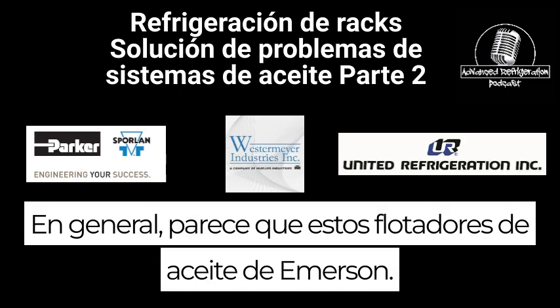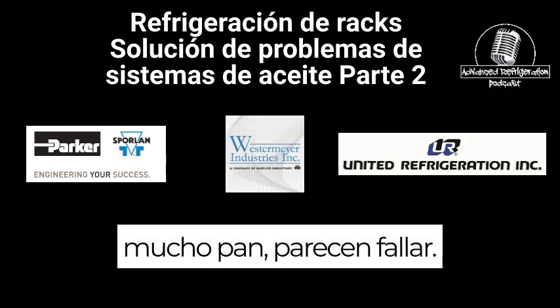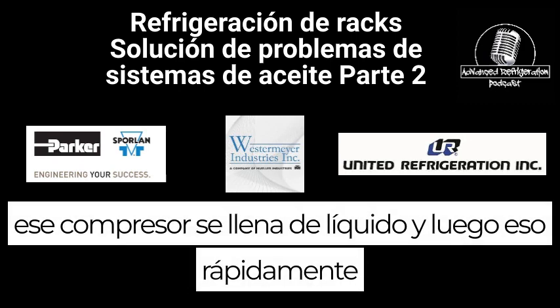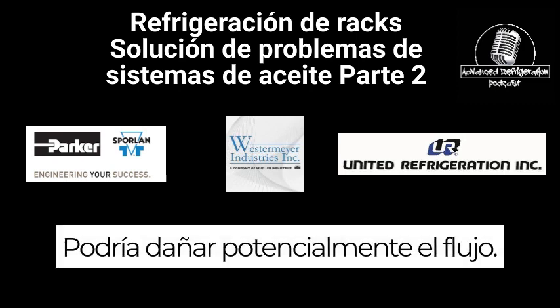Generally, it seems like these Emerson oil floats, I don't know if you see a lot of them, Bradley, they seem to fail a lot. Well, that could be due to, if you have a rack shut down, basically that compressor fills up with liquid and then that rapidly expands when it goes to start back, could potentially damage the float.